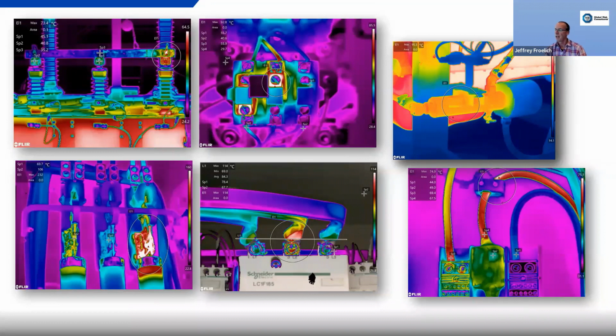Here on the bottom left, what you have is a high resistance contact and a bad, loose, deteriorated connection. It's on the C phase of that fuse clip, and we've got some big-time temperature going on. It's a 600 amp disconnect serving a 300 horse compressor, supplying plant-supplied air. So this is a big downtime if this fails, and it's ready to.